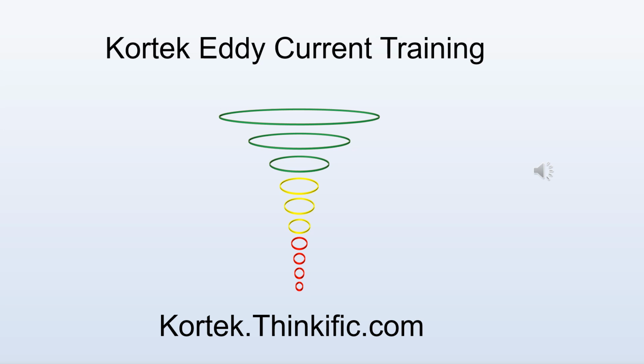Many advancements have also been made in array probe technology in recent years. Eddy current array, or ECA, probes can contain a single band or multiple bands of individual coils, allowing substantially more coverage in a single pass than when conventional single-coil probes are used. Eddy current array probes effectively eliminate the time-consuming raster scanning necessary when pencil probes are used, which has a significant impact on inspection speeds. Probe delivery systems have also improved in recent years.